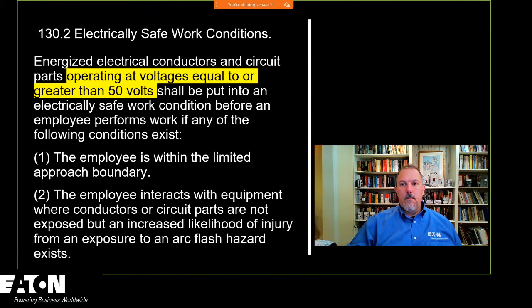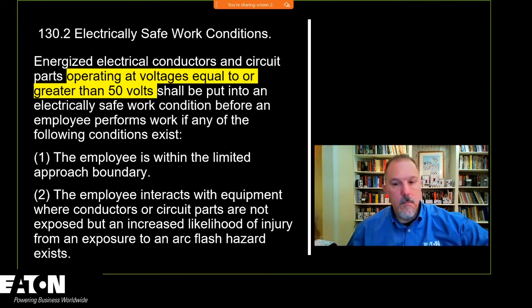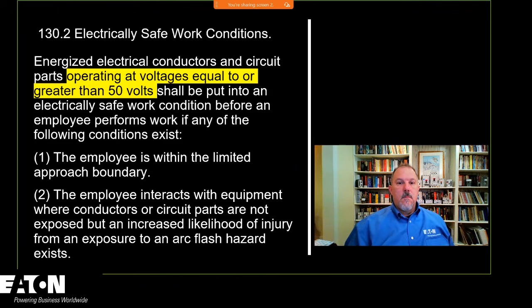Now, if you're at 48 volts, you'll be going to 130.2A, which is titled Energized Work. That's where you get to what I like to call the justification thresholds, okay? Because this is where we tell you that the employer can determine justified work based upon additional hazards or increased risk, or infeasibility, normal operating condition, and A3 gets you into operating at less than 50 volts. And in many cases, if we do have a 48 volt source, for example, people believe that they don't need to do anything at all, and that's not true.